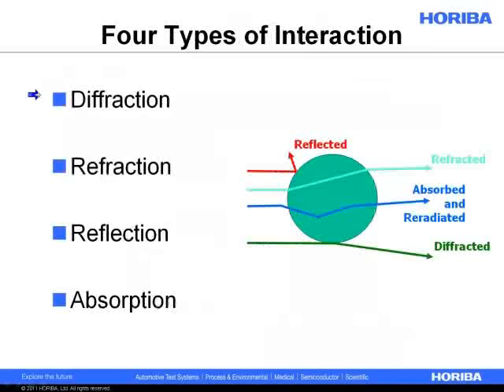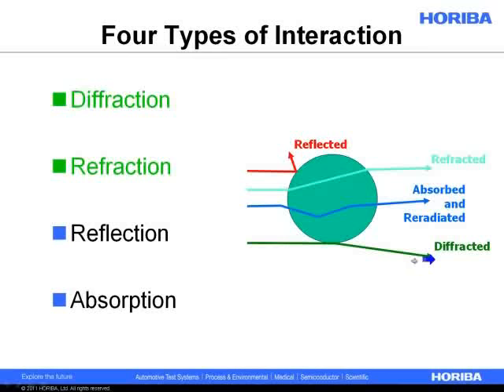There are four different types of interaction between light and a particle: diffraction, refraction, reflection, and absorption. The first two are the good ones. We like diffraction and refraction because they give us useful information — we can tell something about the size of the particle. Diffraction, also called edge diffraction, is where the light hits the edge of the particle at the tangential surface, changes angle, and changes intensity. That's the very fundamental core principle of how the measurement works.